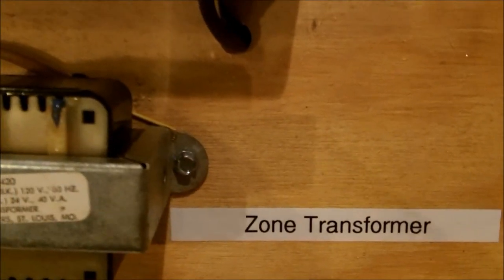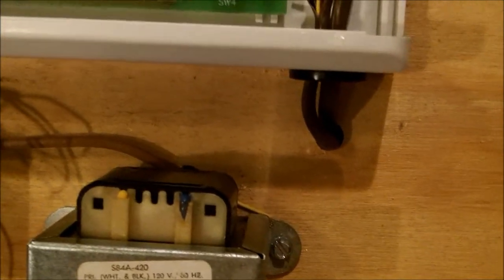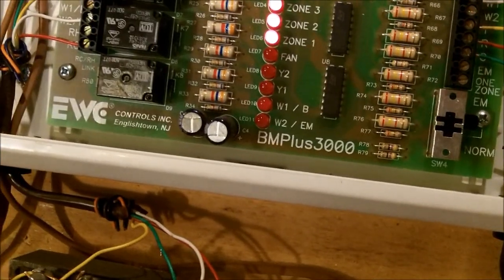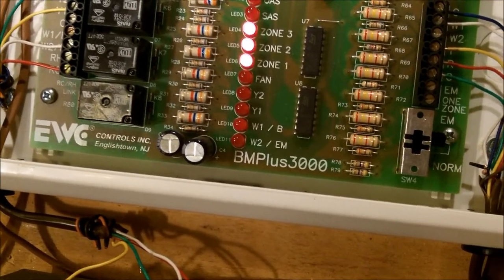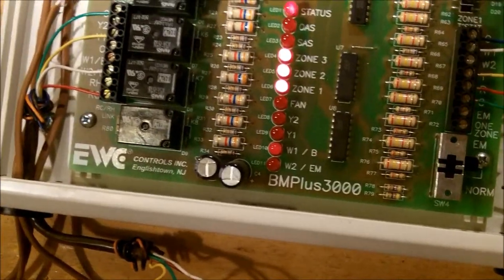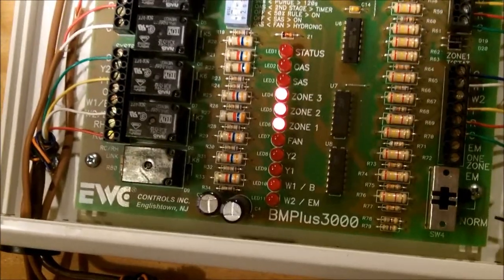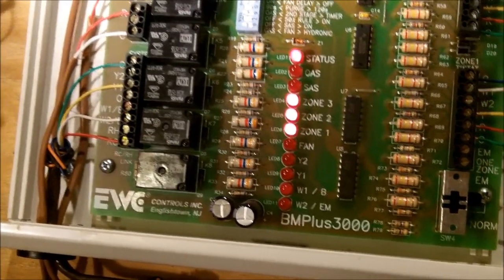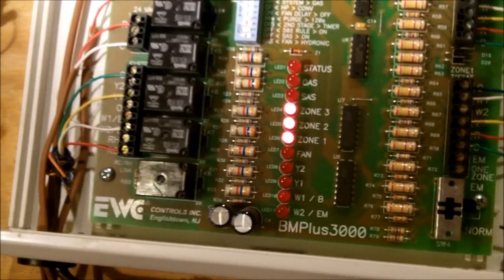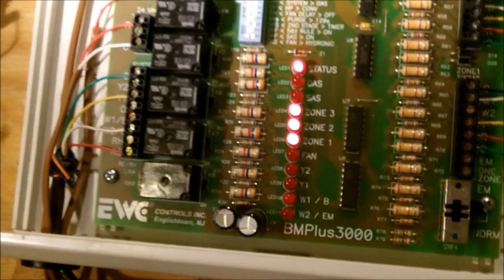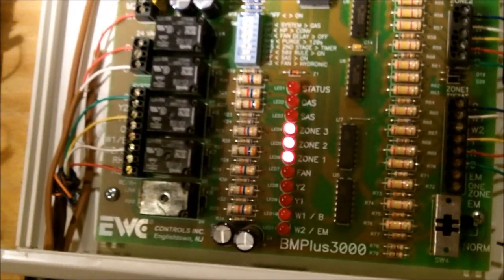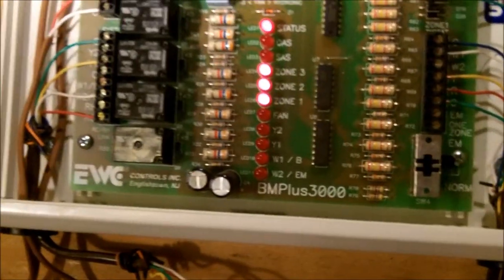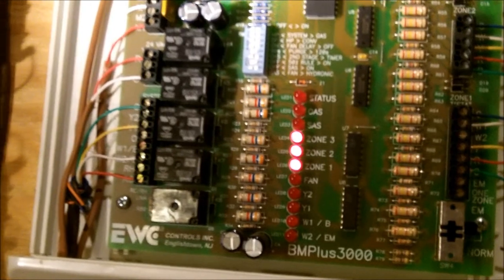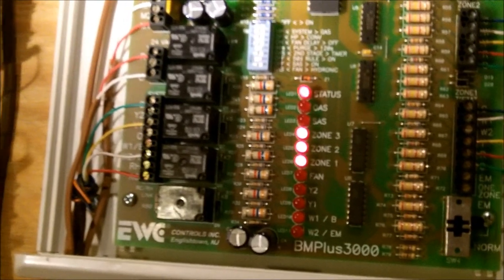Now, while we're waiting on that, the zone transformer, you always need a zone transformer, always. Anytime if you don't have one, you will have problems on your zone system, and if you do and you don't understand what's going on, as soon as you call tech support, they're going to ask you, do you have a separate transformer on your zone board? If you tell them no, the first thing they're going to say is go add a transformer and then call us back. So save yourself some time, save yourself some aggravation. Always add your transformer on any zone board, whether it be EWC, Aprilaire, Lennox, or whoever. Just go ahead and add a transformer.